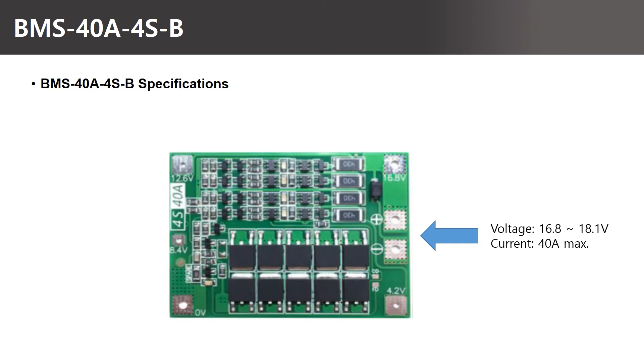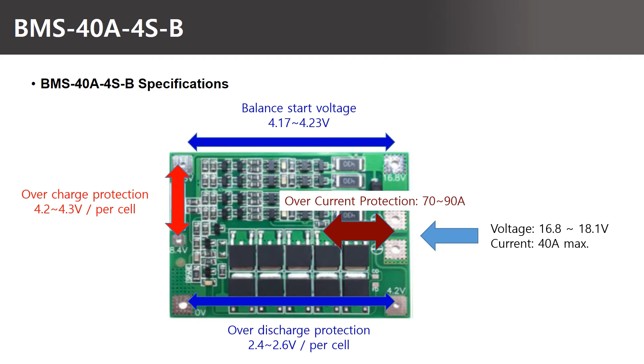Protection is also provided on a per-cell basis. When charging, this BMS protects the cells when the voltage exceeds 4.2 volts. When discharging, it protects the cells by disconnecting the path to the load when the voltage decreases to 2.4 volts. Balancing between cells starts when a cell voltage falls in the 4.17 to 4.23 volt range, meaning this BMS supports balancing between cells while it is being charged.